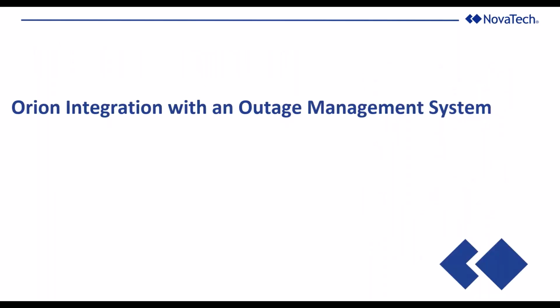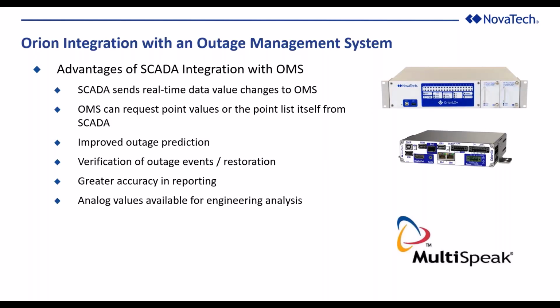So let's chat about SCADA and how we integrate that with an OMS system. Some advantages of SCADA integration. What does it allow to happen? What it boils down to is that SCADA can send real-time unsolicited data value changes into an outage management system, and vice versa, two-way communication. The OMS can request point values, or really it can even request the whole point list itself from SCADA. So we can send the whole point list, which simplifies assigning points to that GIS model, or to that hierarchy of devices, quite a bit.